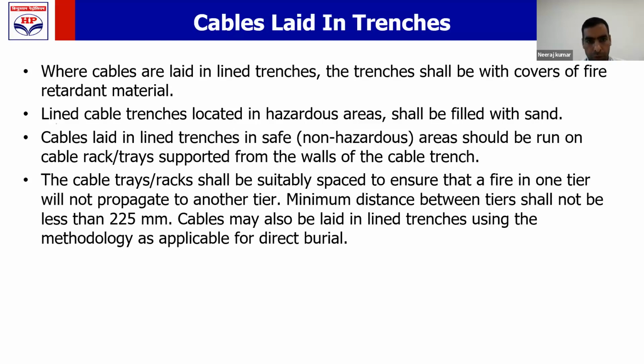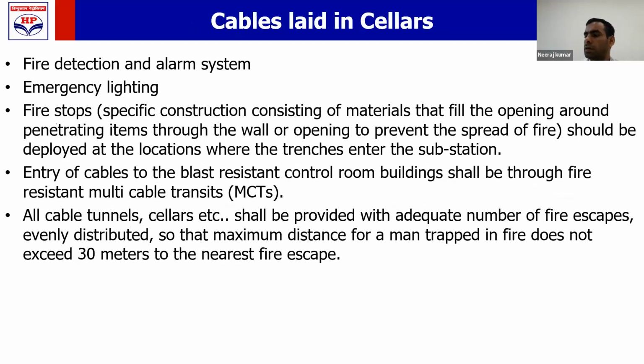You can simply put your cables on the cable trays or racks, which will be installed on the wall of these trenches. But the minimum distance requirement is still there. Even though you are not filling sand, the minimum distance between the different voltage cables shall be 225 mm. These cables shall be laid on the trays, and the trays shall be mounted on the wall of the trench. This is how the cable trench shall be made in the safe area and hazardous area.